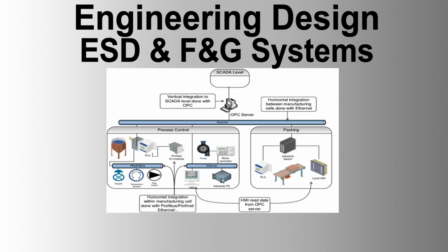System functional requirements. The ESD F&G system shall incorporate emergency shutdown systems and fire and gas systems within a fully integrated, independent, standalone unit which interfaces with the DCS for status and alarm monitoring. The ESD F&G system will have individual processors for ESD and F&G operations with separate I/O, hardware, and software so that a failure of an ESD or F&G element does not affect the other.